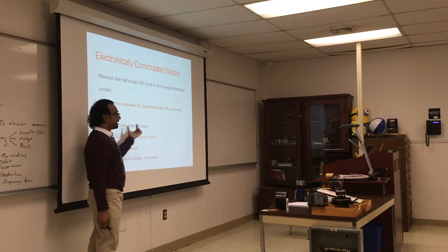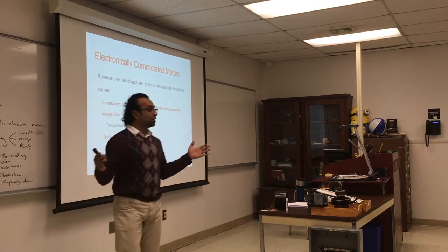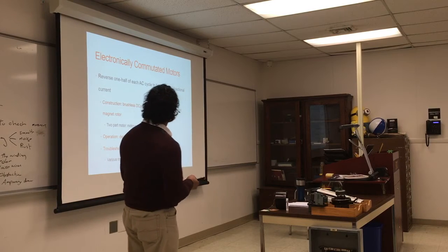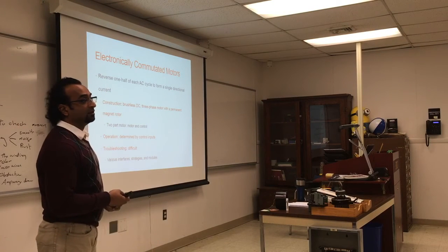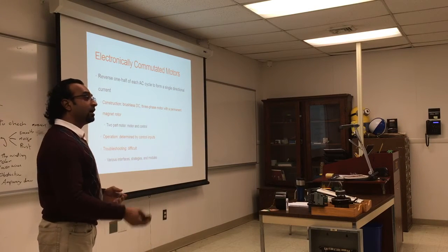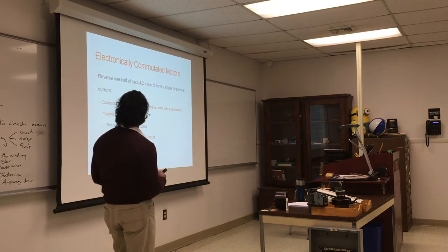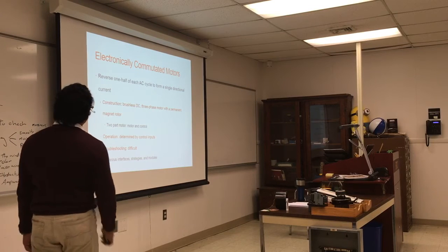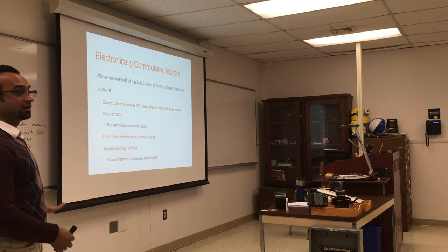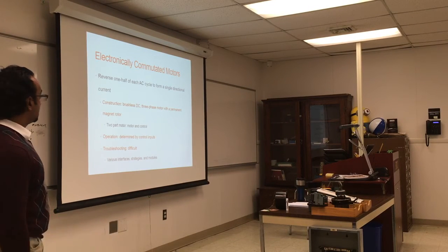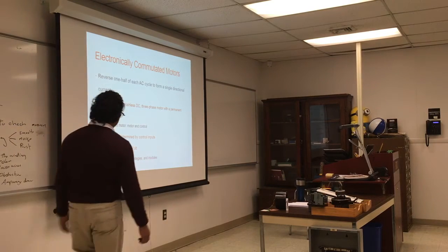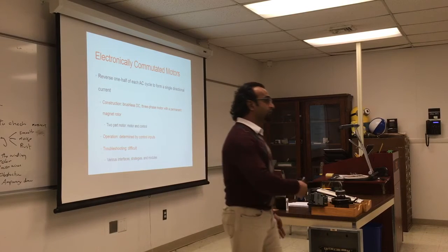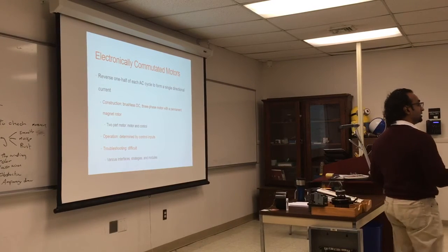There are two parts: a motor and a control. Usually there's a big control box outside of it, and it has a program in it. So they're really hard for us to diagnose. Usually they are sent out to the manufacturer to fix. But again, you can check the visible things on our side. You can look at the bearing, you can look at the wiring, and see what's happening. They have various interfaces and models, so it can be slow or fast, with different torque and different rotation.